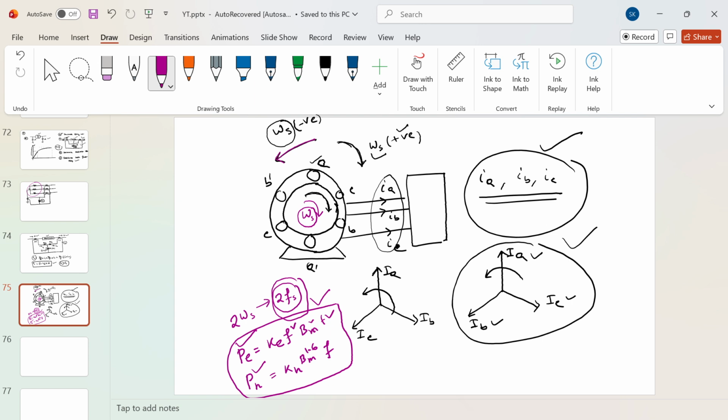So we'll be having some measurement in these lines, and if the negative sequence component is significantly high, or more than the specified value, then the negative sequence relay will send the trip signal, and my circuit breaker will simply trip the lines. This is how it operates. So the bottom line is, by having a negative sequence relay, you can protect your synchronous machine from overheating.